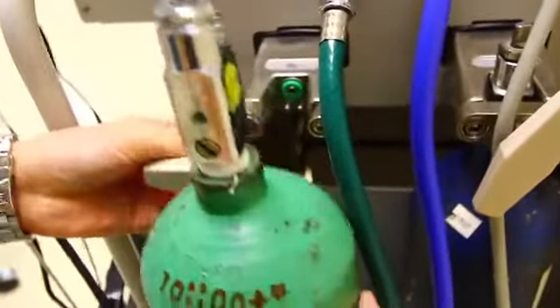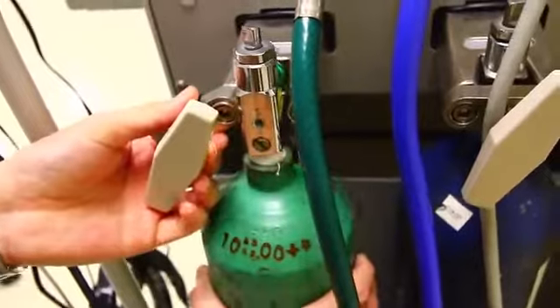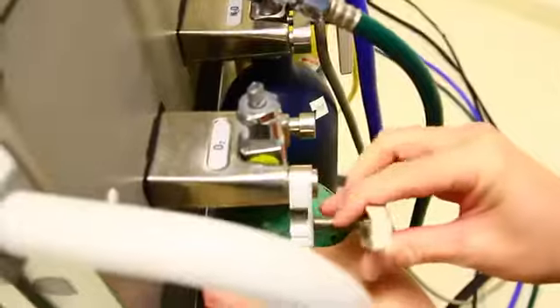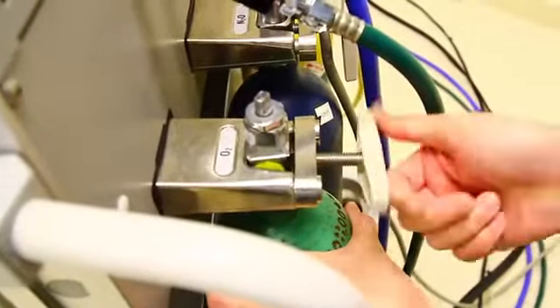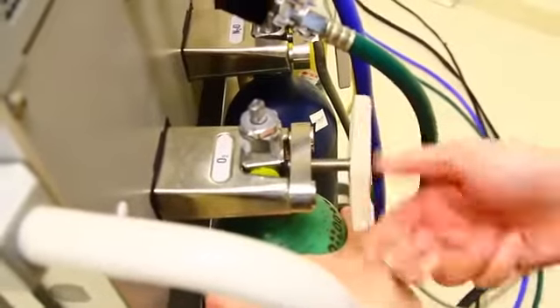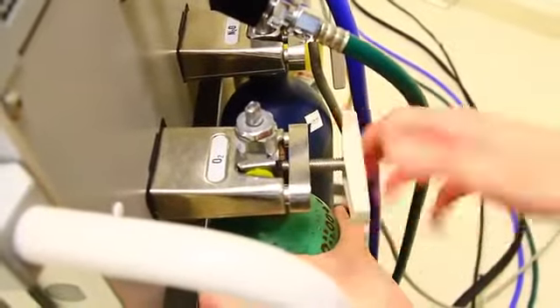Now reinsert the oxygen tank and align the pin index safety system. Replace the latch and turn the handle clockwise until hand tight. To engage the lock, push down. To disengage, pull up.